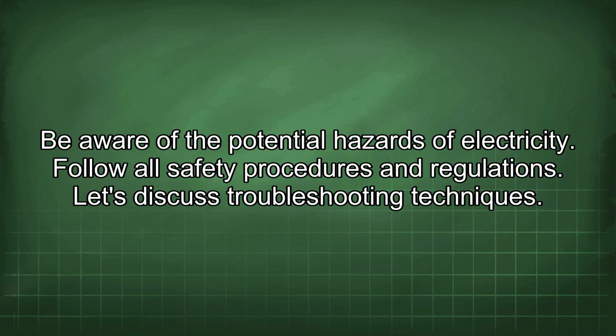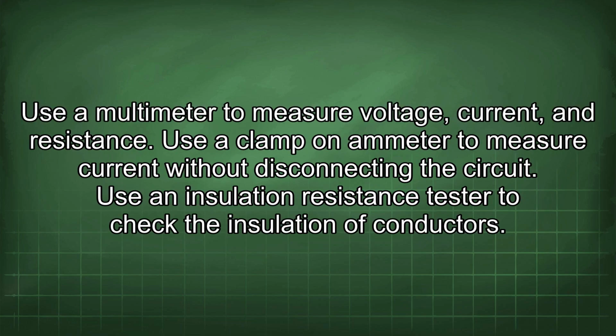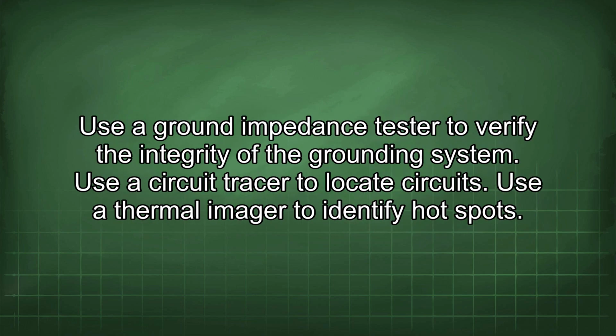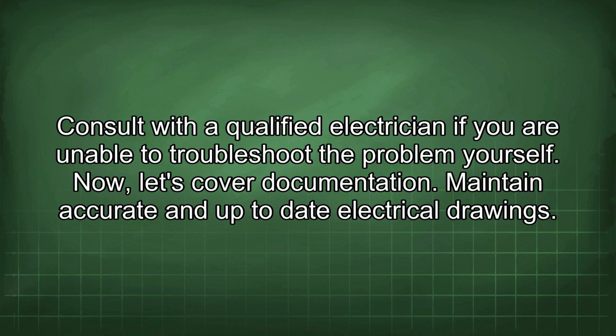Let's discuss troubleshooting techniques. Use a multimeter to measure voltage, current, and resistance. Use a clamp-on ammeter to measure current without disconnecting the circuit. Use an insulation resistance tester to check the insulation of conductors. Use a ground impedance tester to verify the integrity of the grounding system. Use a circuit tracer to locate circuits. Use a thermal imager to identify hotspots. Consult with a qualified electrician if you are unable to troubleshoot the problem yourself.